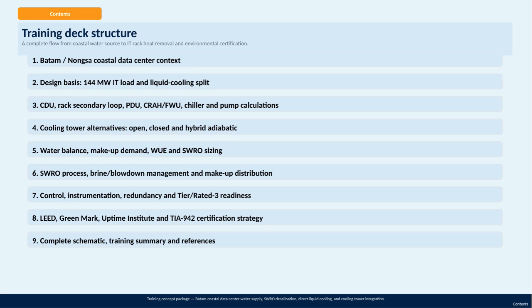The training concept package focuses on the Batam Coastal Data Center and covers critical elements such as a water supply from the sea, SWRO desalination, direct liquid cooling, and how cooling towers are integrated into the system. The deck is divided into 9 key sections. First, we provide the context for the Batam and Nongsa Coastal Data Center location. Next, we cover the design basis, including the 144 megawatts IT load and how the liquid cooling is split.